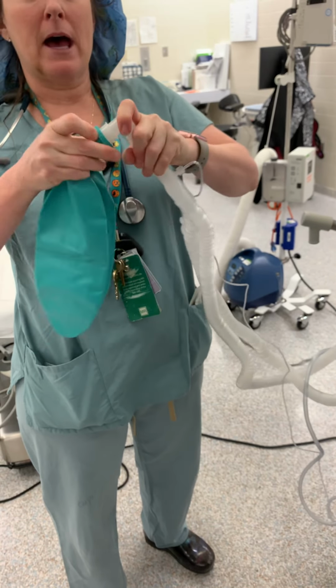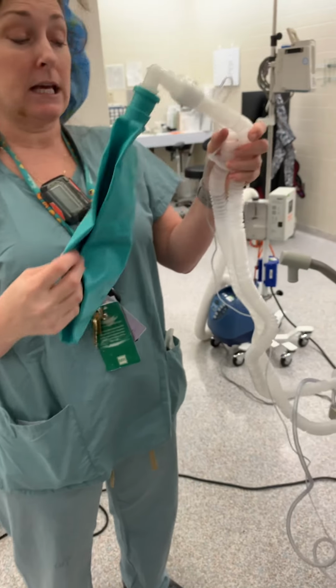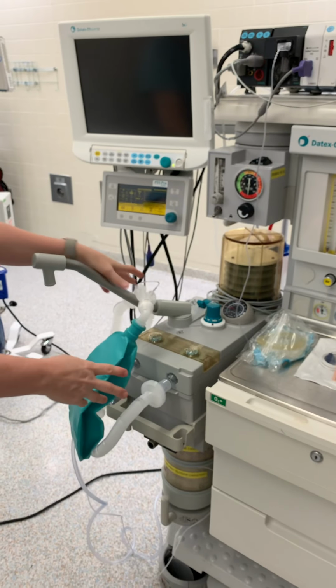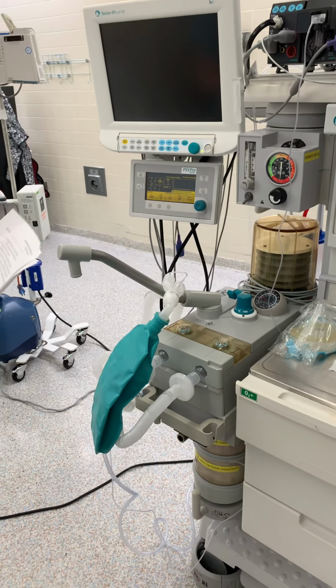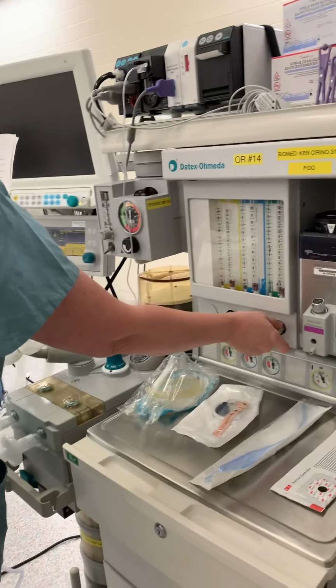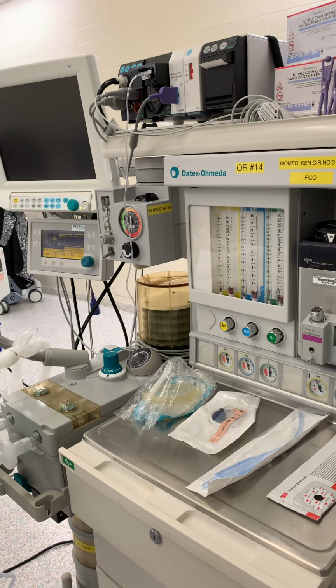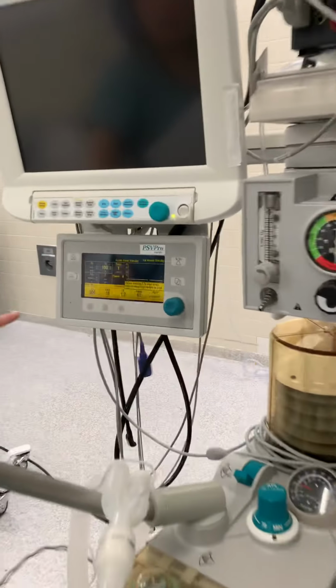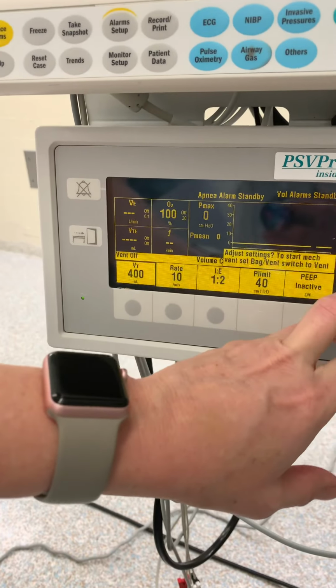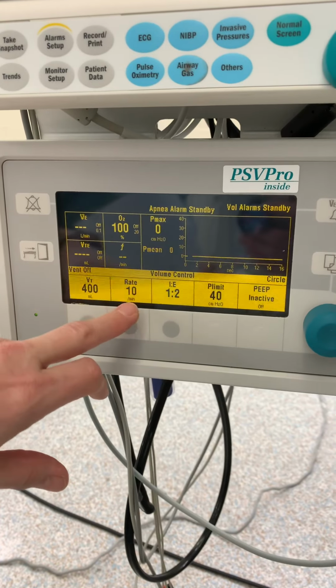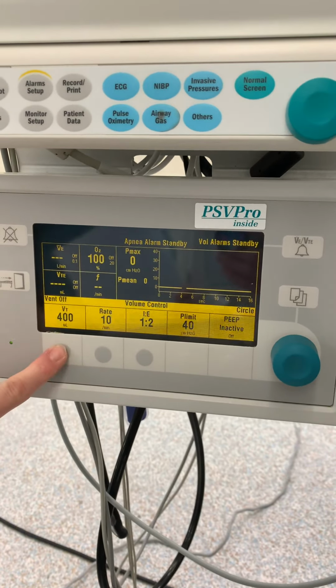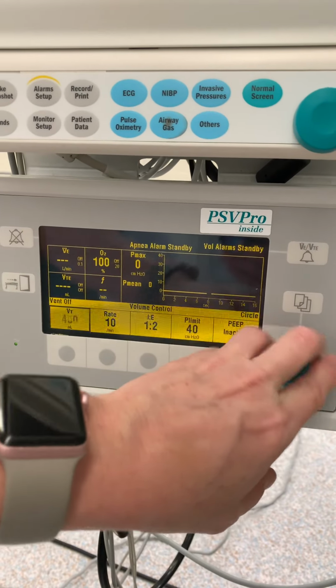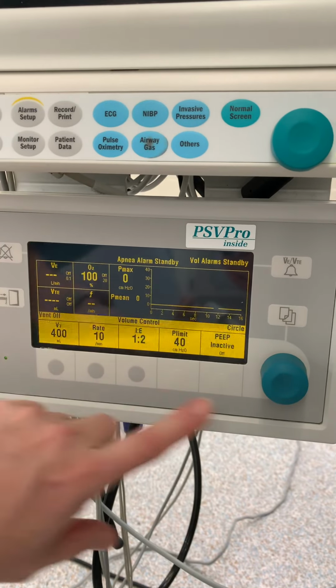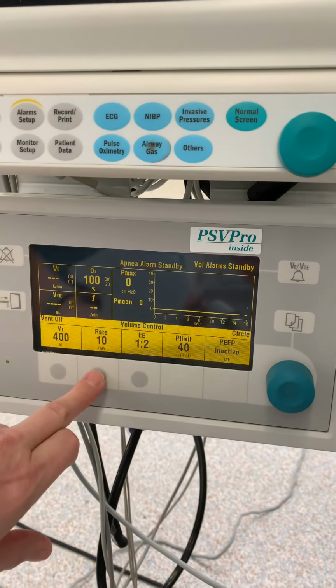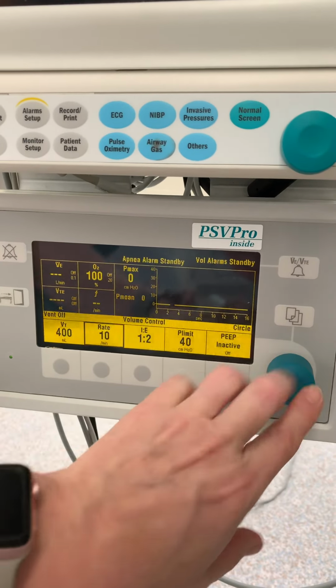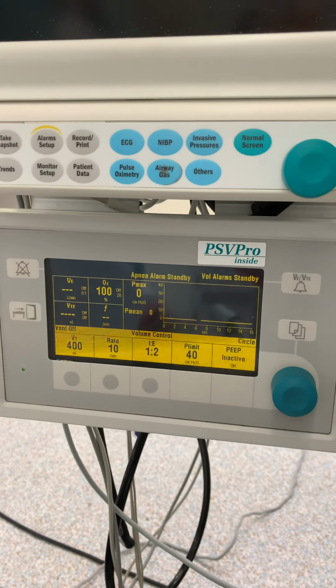So the reservoir bag or the breathing bag is going to act like a lung. So we're just going to keep that there, and following down with the flow meter at 0, you want to go ahead and turn on your tidal volume and your rate. Now, the manufacturer recommends that when you test this portion, you have a tidal volume of 400 and a rate of 10. You select this by going to the button underneath, it highlights, and then you can toggle up and down. So when you get to what you want, you just select and it stays. Again, rate, select the button underneath, toggle to 10, select, and now you have your settings.